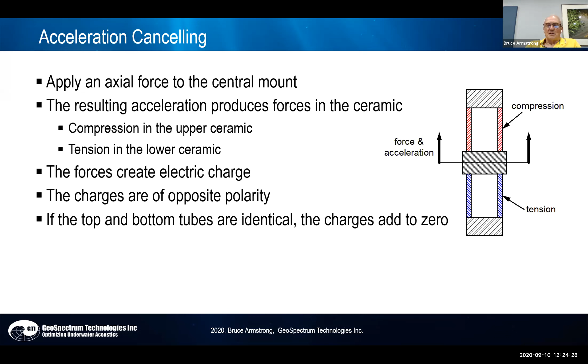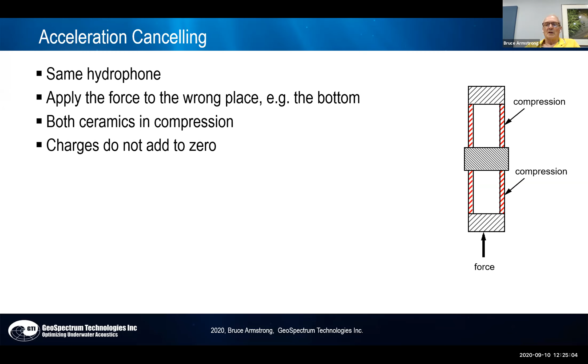So the summation of this, or here's an example of it: you can take an acceleration canceling hydrophone and actually make it non-acceleration canceling if you put the force in the wrong place. Take the same phone, and if you put the force on the bottom of the hydrophone rather than on the central mount, both ceramics go into compression, and then your charges don't add to zero. So just because you've purchased an acceleration canceling hydrophone, you still have to mount it properly in order for it to work as intended.